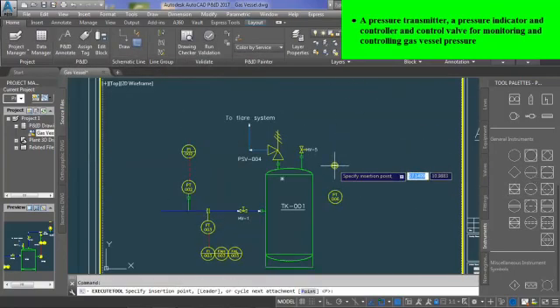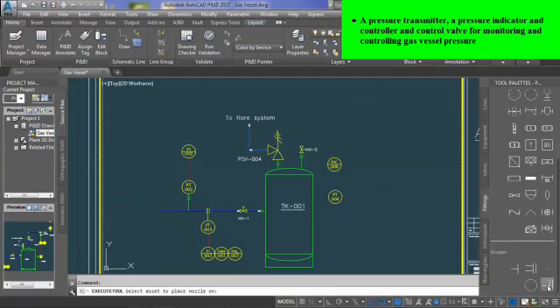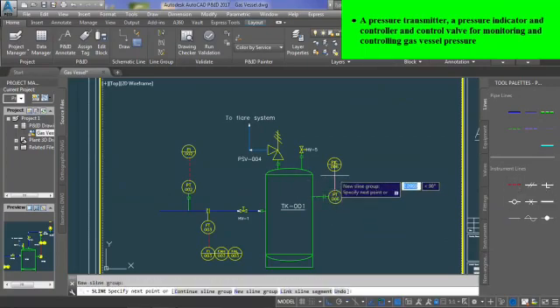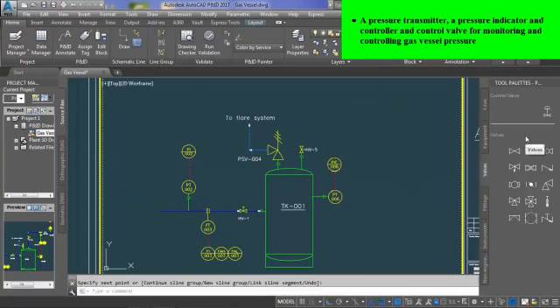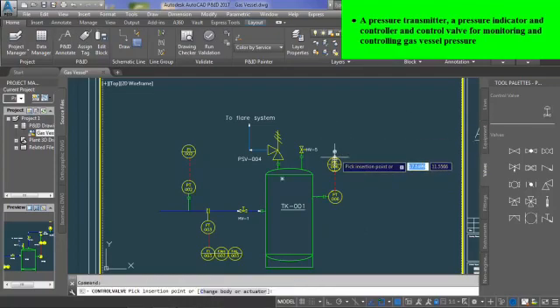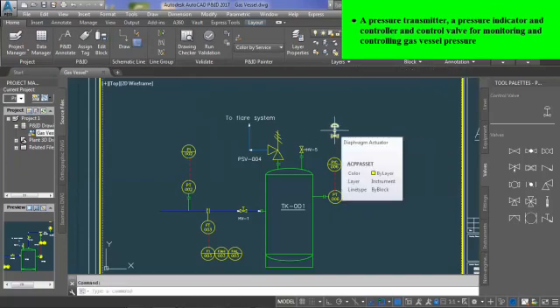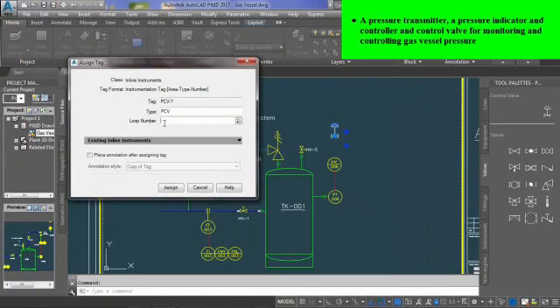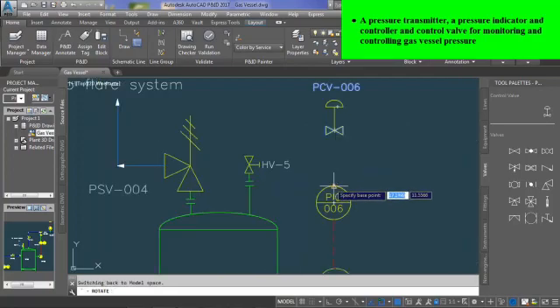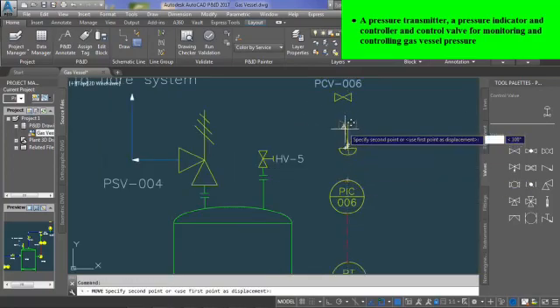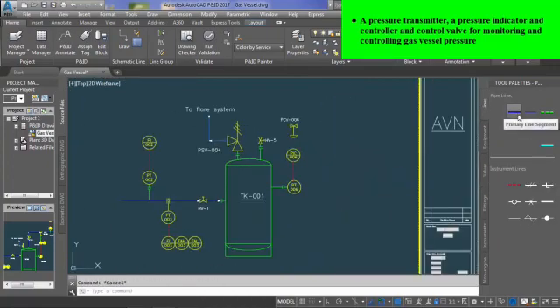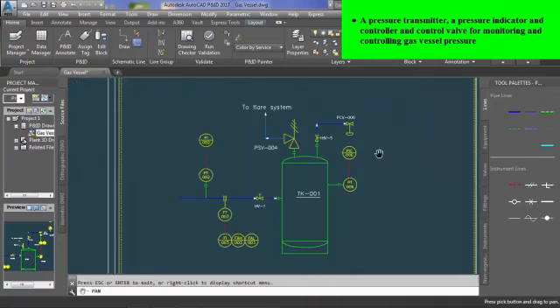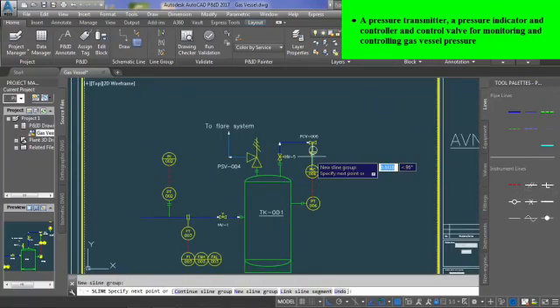After that, add pressure indicator controller and assign tag PIC-6. Then control valve, this time is a diaphragm valve with pressure control valve or PCV-6 tag. Join the hand valve with the control valve through a pipeline, and then the pneumatic line is drawn from PIC to the control valve.